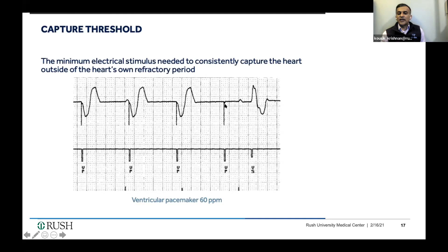So what can affect capture? There are acute and chronic factors that can affect capture. This is primarily related to what's happening in the device, in the lead, and at the interface between the lead and the myocardium. So we'll talk about the lead myocardium interface. If the lead is not making good contact with myocardium, there's inefficient current transfer to the myocardium, which will prevent capture. What if the lead is making good contact with the tissue? What could impact capture in that respect?